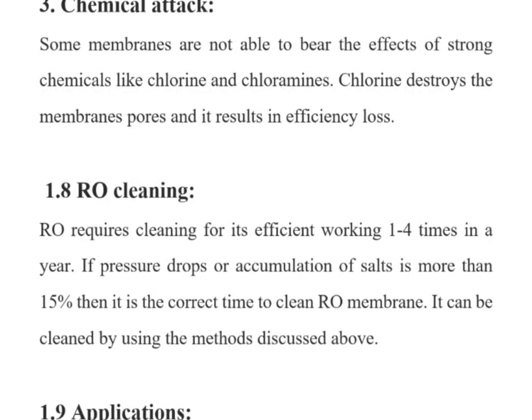Next one is chemical attack. Some membranes are not able to bear strong chemicals like chlorine and chloramines, so these destroy the membrane pores and its efficiency is totally lost. So we have to check these chemicals.